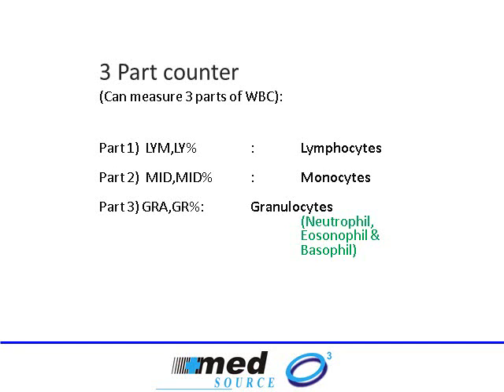On the other hand, a five-part hematology analyzer will also be able to measure the individual amounts of neutrophils, eosinophils, and basophils. So a three-part cell counter gives you results for lymphocytes, monocytes, and granulocytes, while a five-part gives you lymphocytes, monocytes, neutrophils, eosinophils, and basophils. Both the HumaCount 30TS and EuroCount TS are three-part hematology analyzers.